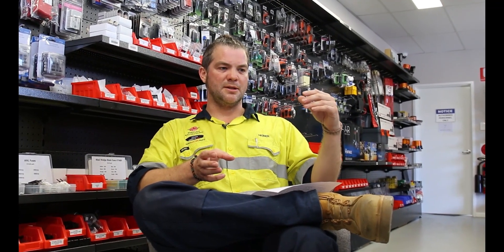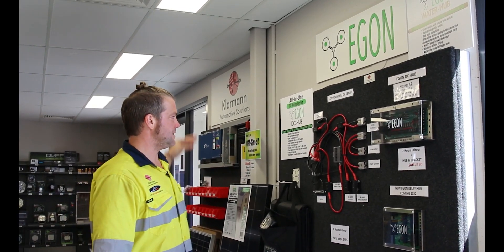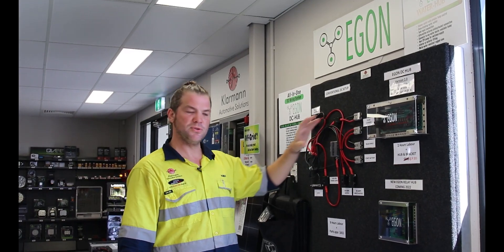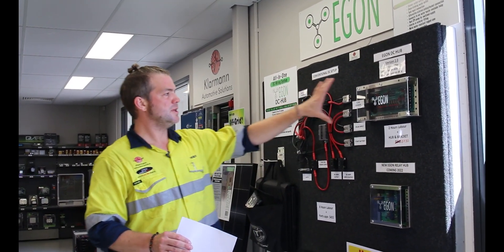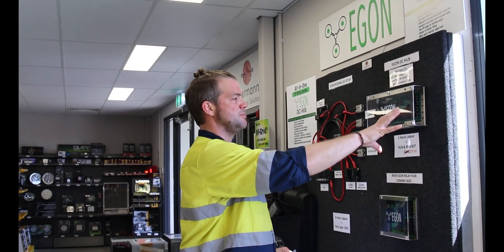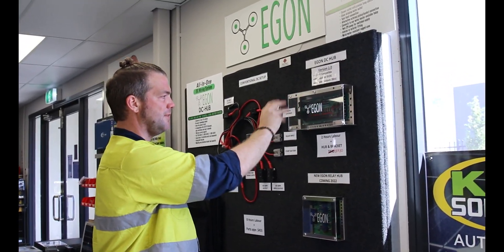What I've explained so far is a conventional power distribution system. Those of you who've been following us know that we've got our own approach — the EGON range, the EGON DC hub. Everything I just talked about — battery positive into the big ANL fuse, to your large inverter, then a main circuit to your power distribution with midi fuses, maxi fuses, fuse holders, and bus bars for grounds — you can do all of that with this as well. You just have your main feeds going in and all your power distribution and fusing is done right there. Voltage drop is minimized because everything is so close together.